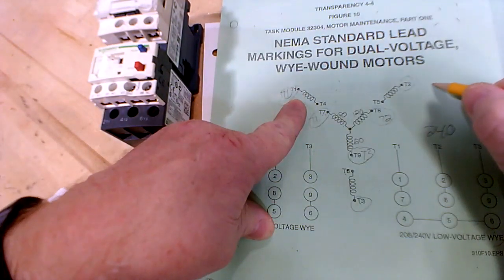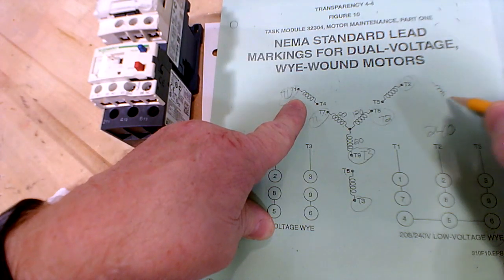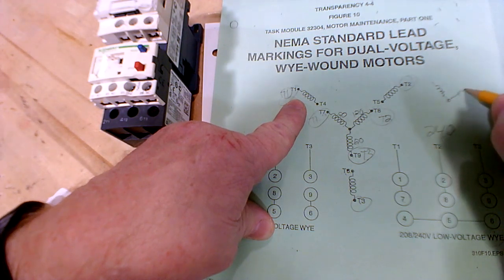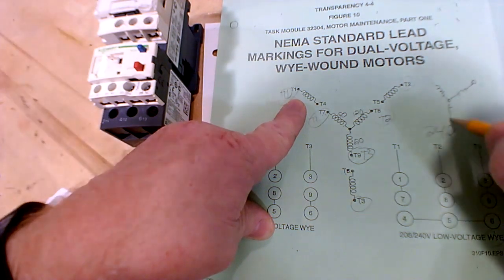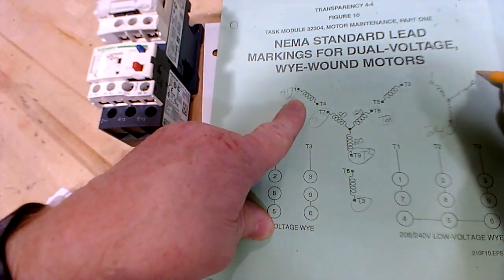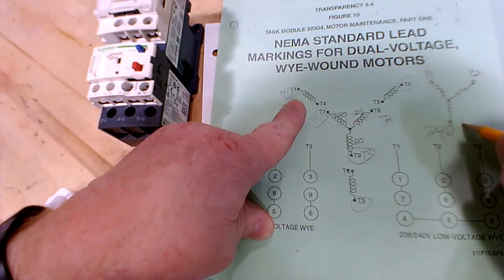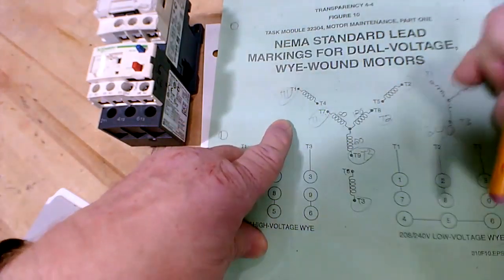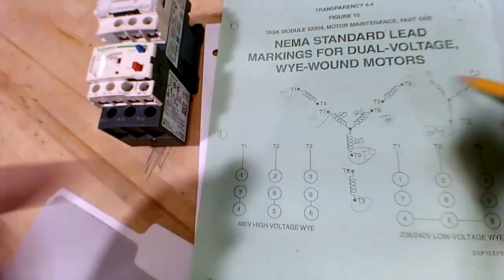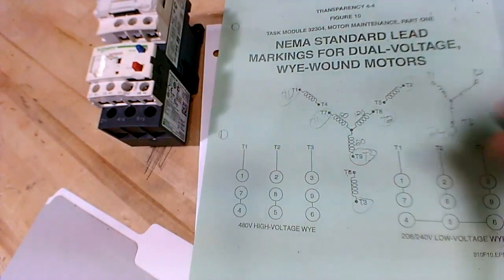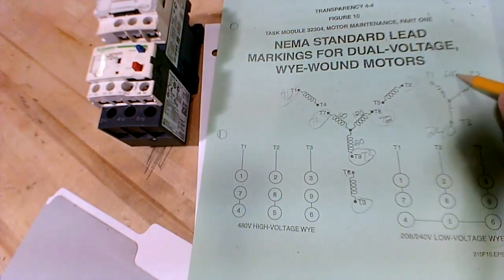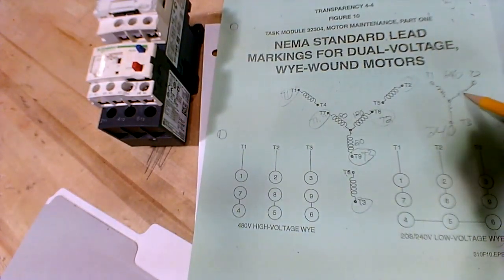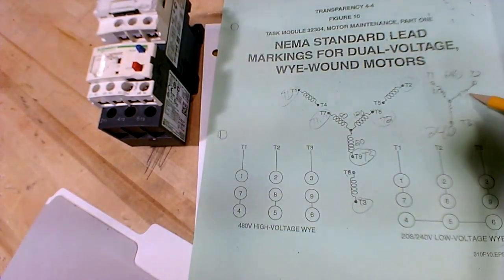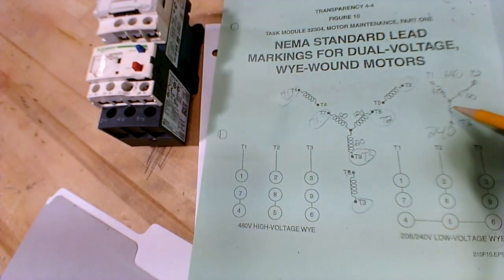Let's draw the windings here. You have here, there, going, winding here, out, winding there. And so you have 1, 2, T1, T2, and T3, right? These 3 are out here now. So if I'm going to get 240 across this outer wire, right? That's out here, 240. So if that's so, then I have 2 in series. How much are they getting a piece? They're getting 120, 120. And I measure from here to here. What do I get? 240.